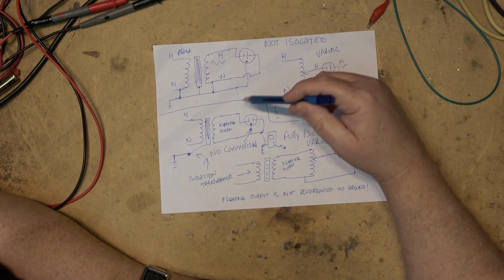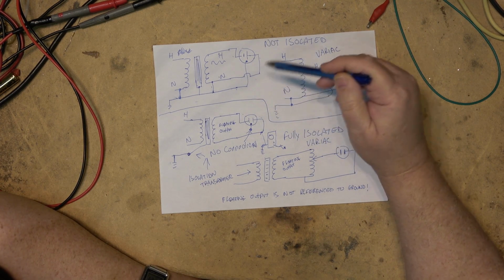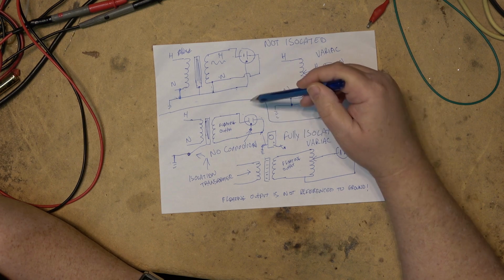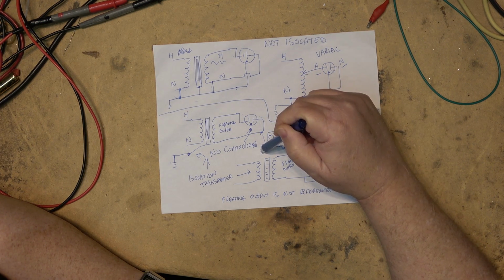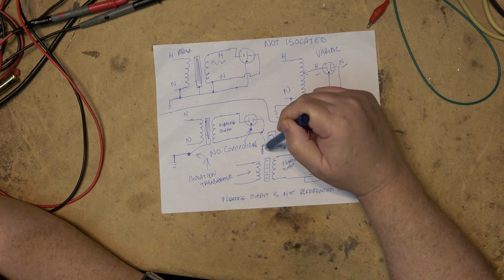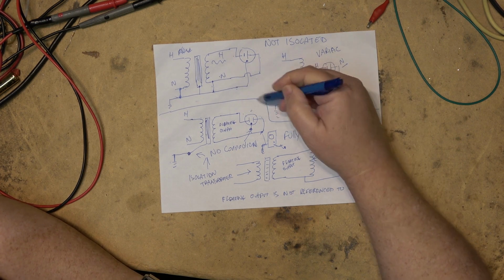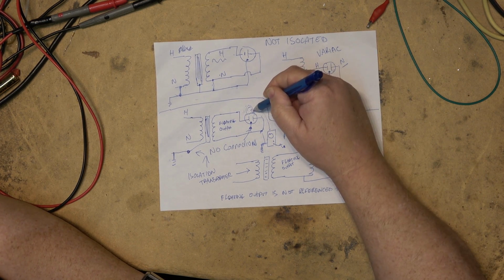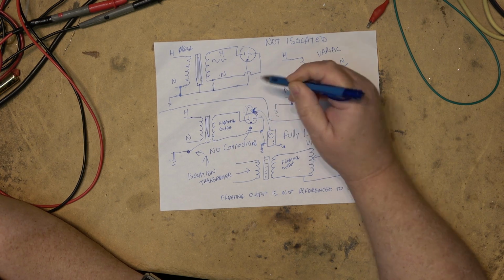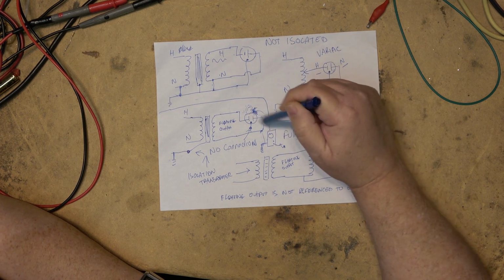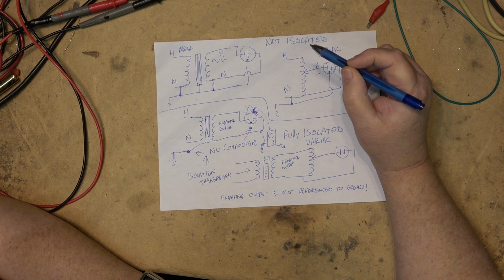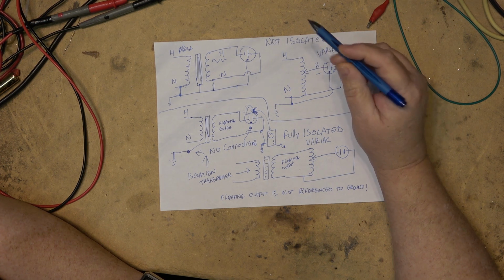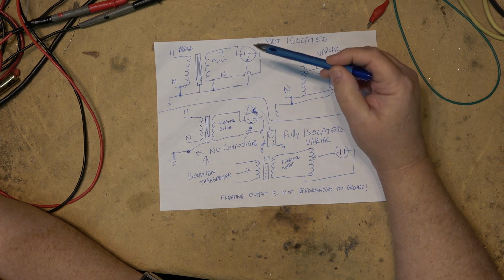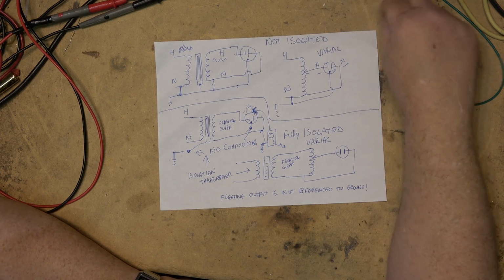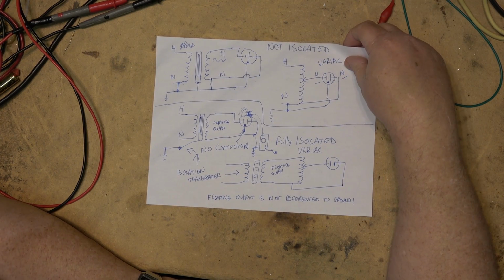So if you're hooking up an oscilloscope and testing for leakage or whatever, or you want to be safe, remove the ground pin off the scope cord, or better still, plug your scope in here and power it from the isolated output, because that way you've removed the ground reference. But again, be safe, as they say. It's a safety must if you're dealing with any line-connected equipment, if you're working on anything that you could get a shock from.